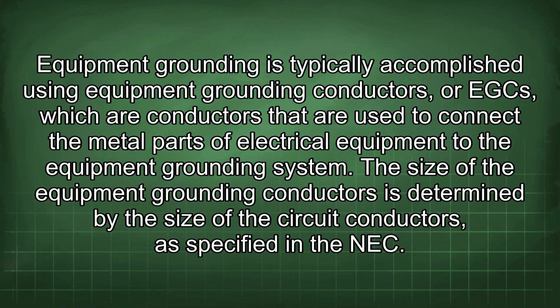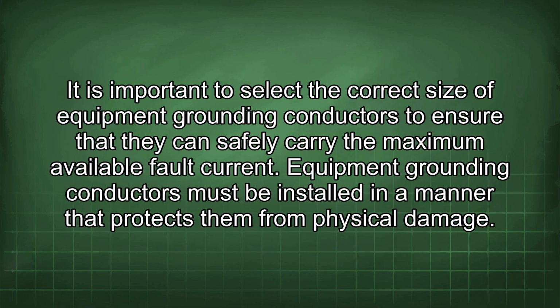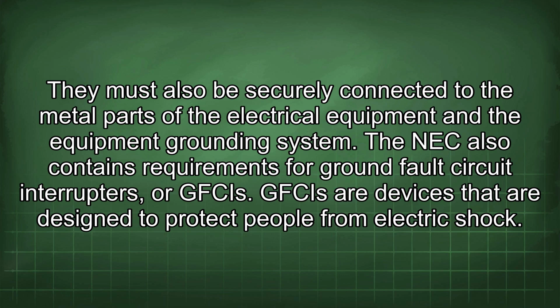The size of the equipment grounding conductors is determined by the size of the circuit conductors, as specified in the NEC. It is important to select the correct size of equipment grounding conductors to ensure that they can safely carry the maximum available fault current. Equipment grounding conductors must be installed in a manner that protects them from physical damage. They must also be securely connected to the metal parts of the electrical equipment and the equipment grounding system.